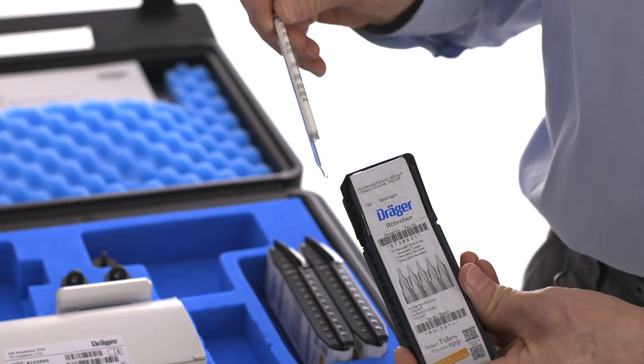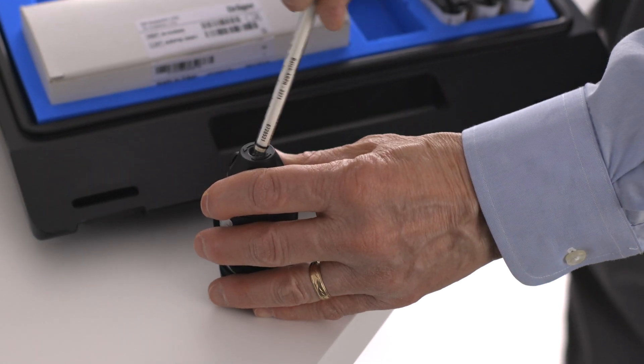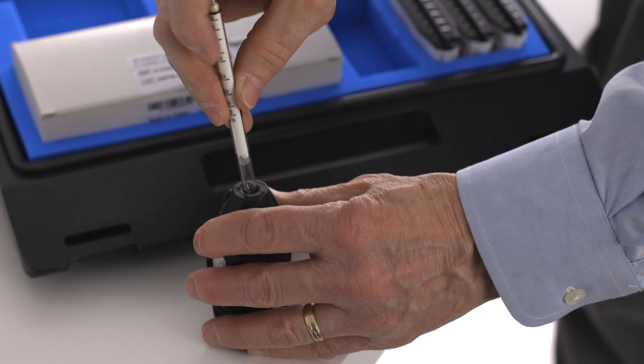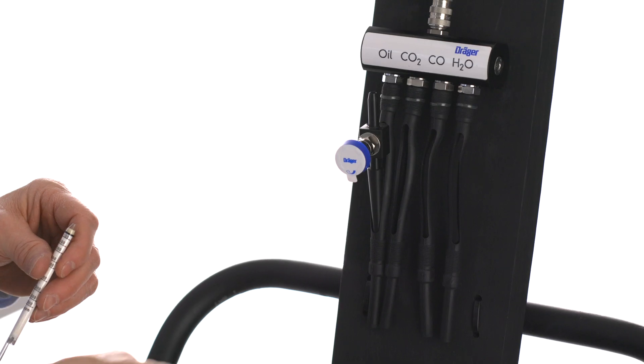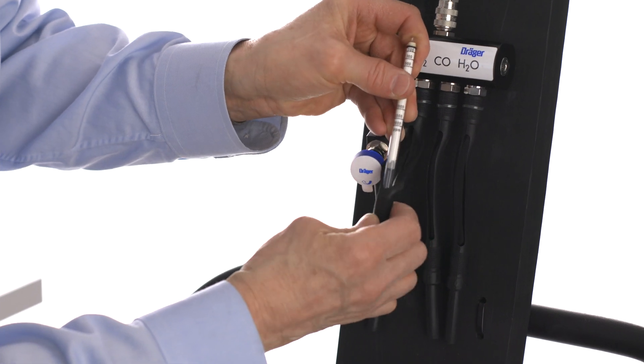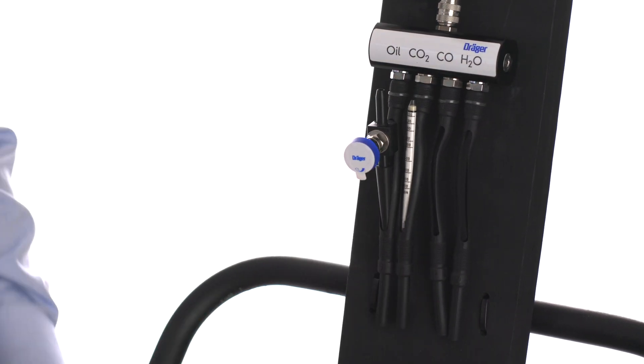Select one of the carbon dioxide tubes from the case. Score and snap off the tips using the tube opener. The arrow on the tube indicates the direction of airflow. Insert the tube into the bottom of the correct holder, leaving the top part disconnected for now.